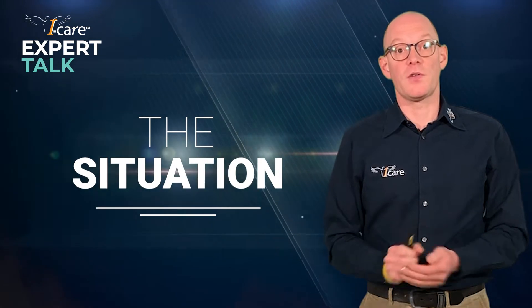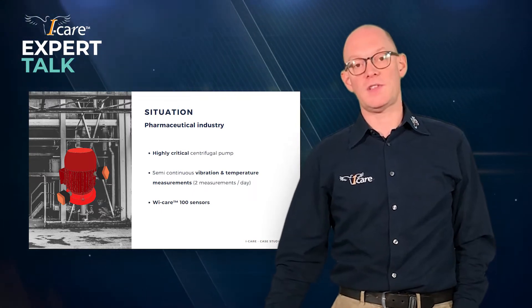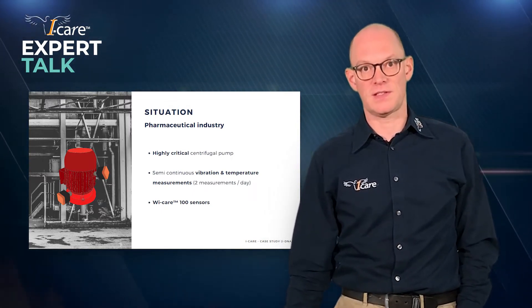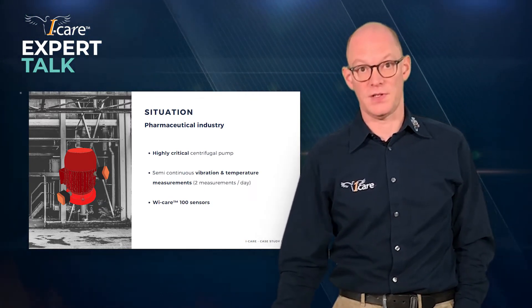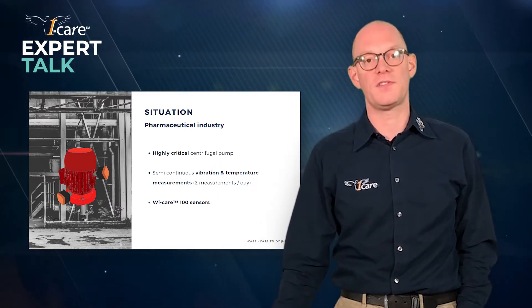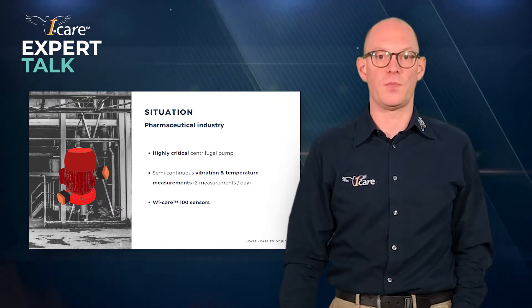The situation we're looking at here is a highly critical centrifugal pump in a pharmaceutical industry. We use a semi-continuous vibration and temperature measurement system named, in this case, the Wi-care 100. It's taking two measurements a day, which is already quite more than what we would do in a lot of other situations by going to the machine and taking measurements with our portable devices.